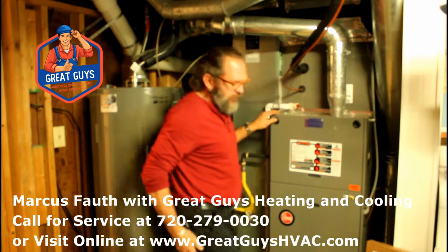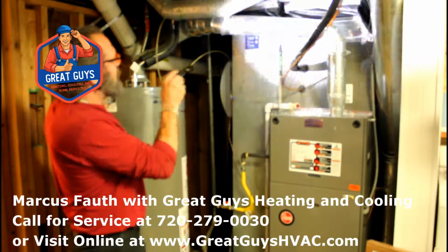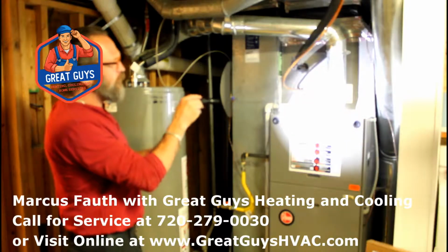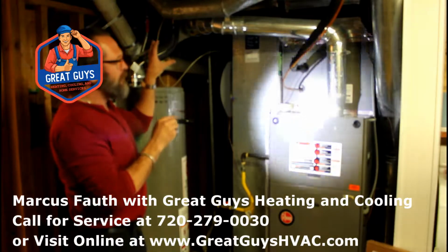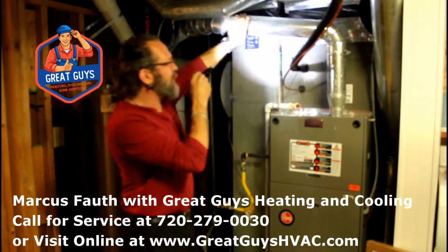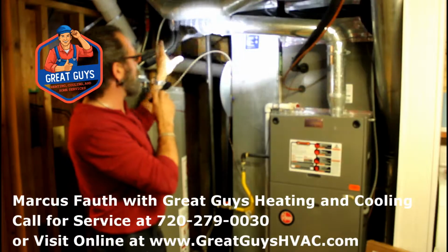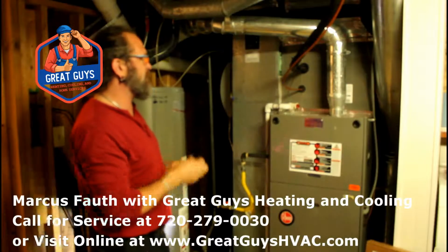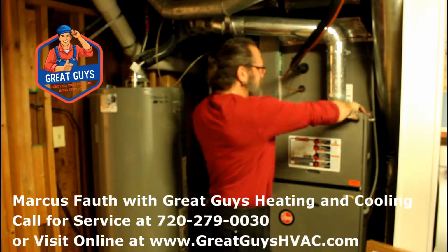When we get here, and I'll try to use my flashlight to point out some of these aspects, we go over the venting to make sure that all of the flue venting that is responsible for removing the gases of the furnace out of the home is sound. This is the area where you would potentially have a carbon monoxide leak. If there was a loose fitting or a rusted point on one of these vents, that would obviously be a major concern. So we do a visual inspection of that first and foremost, and then we dig into the actual components of the furnace.